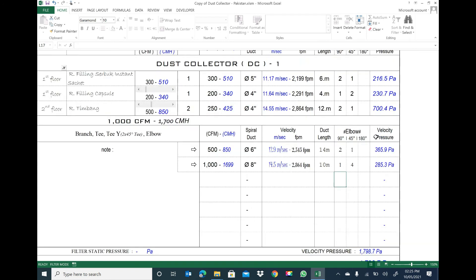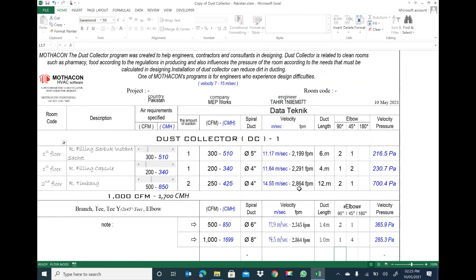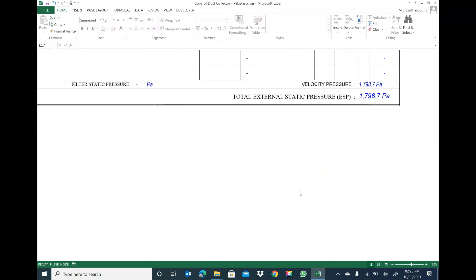The pressure losses are the summation of all clean rooms plus the main duct sections. The dust collector filter section also has its own static pressure — we check with the manufacturer and add it here. Normally it is 600 to 800 Pascal. We add this value, and the final total becomes the external static pressure for the dust collection system.